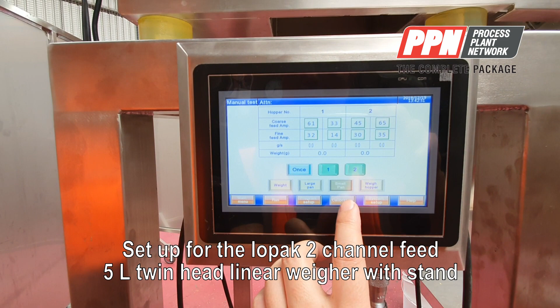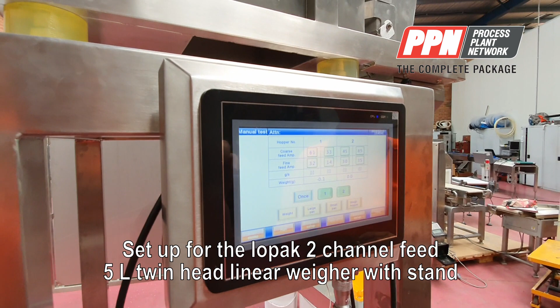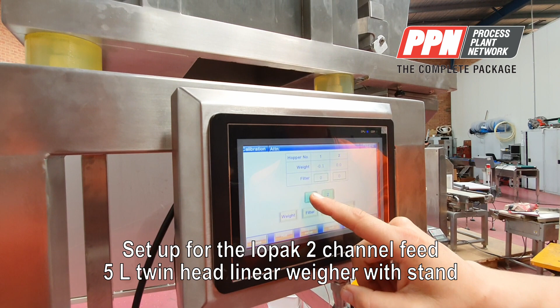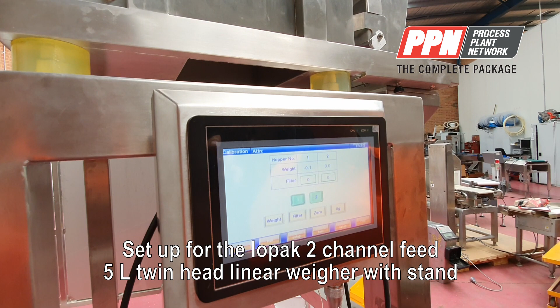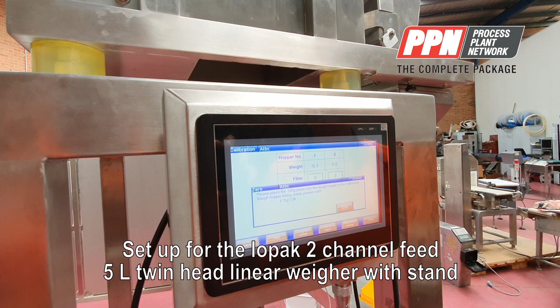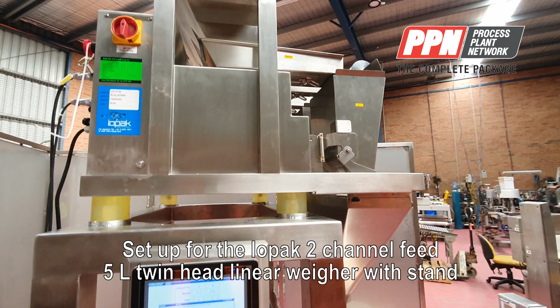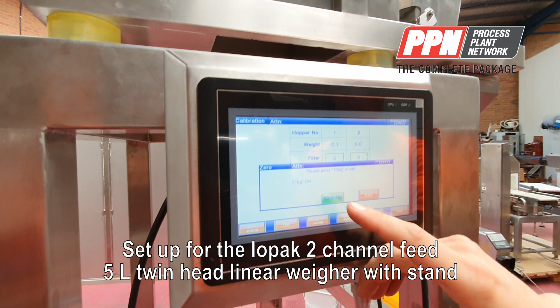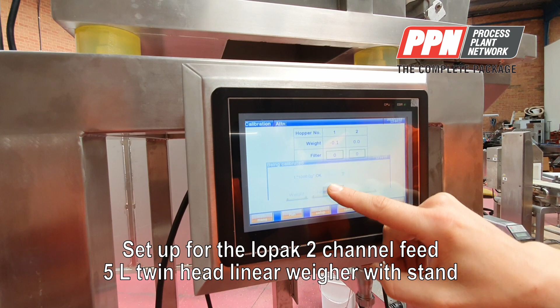What we're going to do now is a calibration. So let's do a calibration for head number 1. Select head number 1. Now we have to zero it, so make sure the bucket is empty while you're doing the calibration, and then you press the next button, and now we'll put the weight on. We are putting a 1 kilogram sample weight onto the machine, so we press 1000 and then press enter. Now the calibration should be complete.